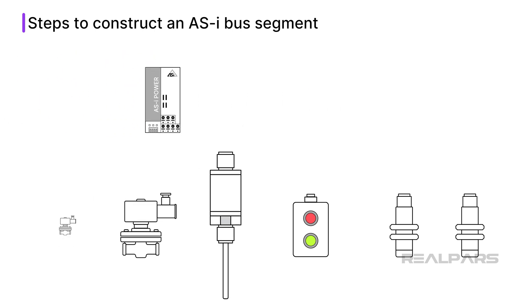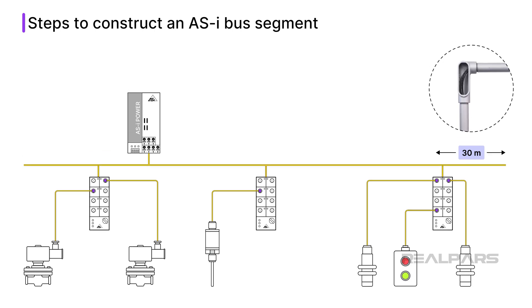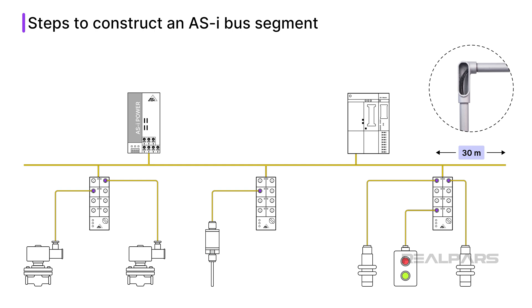Next, I need to see how long my segment will be. I locate where the devices need to go in the process, and since AS-i bus is a trunk and drop system, I determine 30 meters of trunk cable is sufficient to drop the network to each device. I can use special condolets or passive connection bricks to make connections easier. I install the power supply on a DIN rail in a nearby remote I/O panel, along with my AS-i master communication card. I install the cabling from the power supply to the master card.